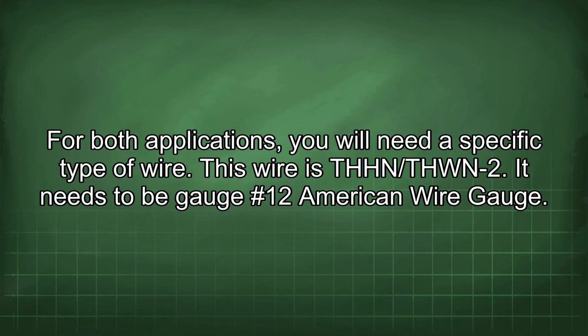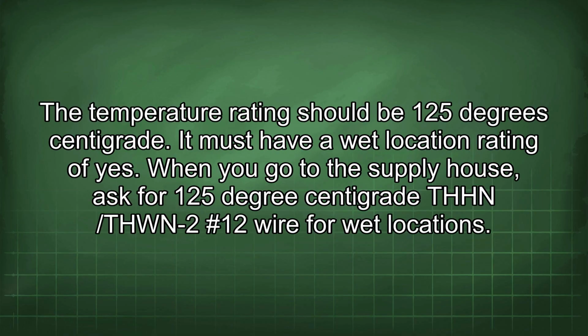For both applications, you will need a specific type of wire. This wire is THHN/THWN-2. It needs to be gauge #12 American wire gauge. The temperature rating should be 125 degrees centigrade. It must have a wet location rating of yes. When you go to the supply house, ask for 125 degrees centigrade THHN/THWN-2 #12 wire for wet locations.